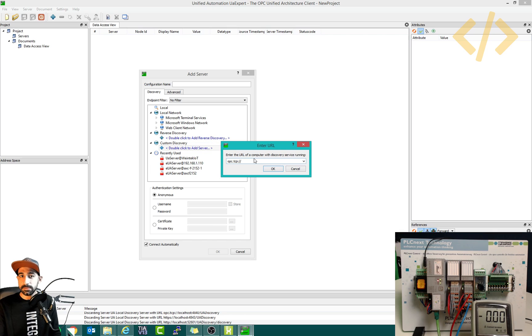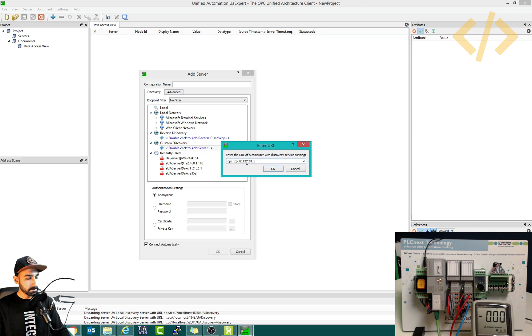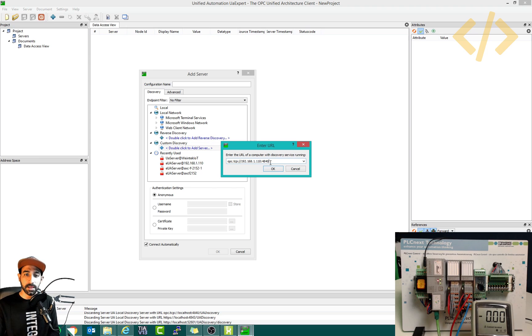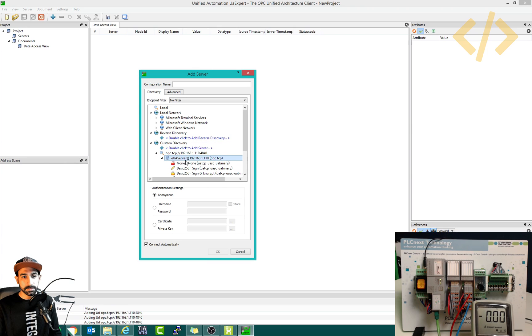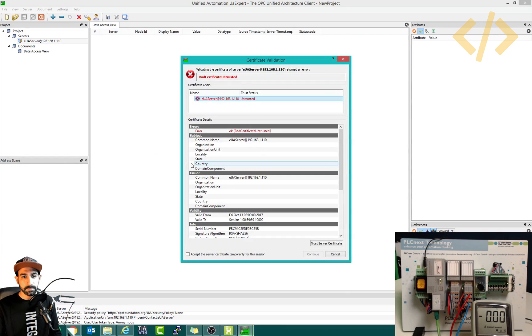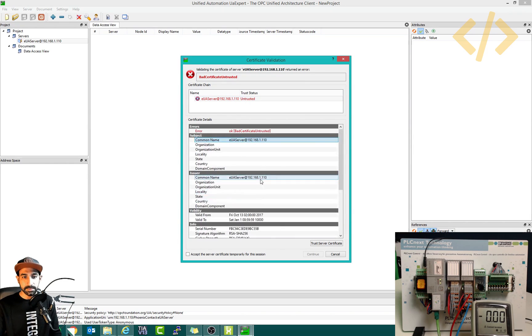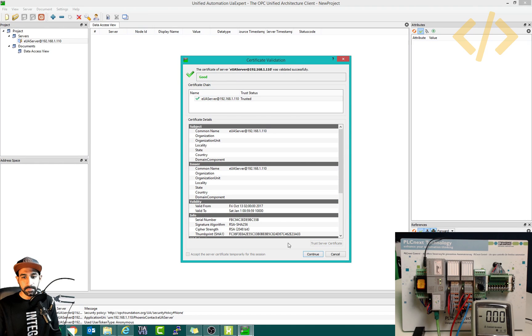If you have any other third-party OPC UA software, you have to enter: opc.tcp:// followed by the IP address of the PLC, then a colon, and the default port for OPC UA which is 4840. This is the port where OPC values are coming. Click OK, then double-click the server entry, select 'none', and it will ask for the certificate. These are certificate details from PLC Next — I say trust and click continue.